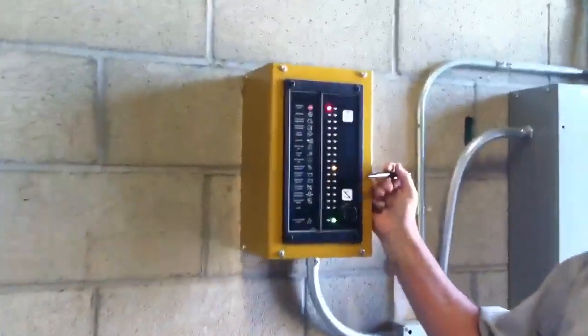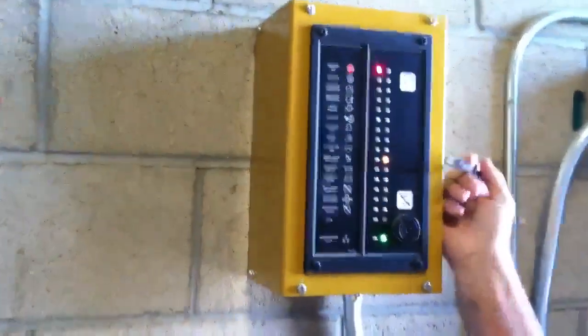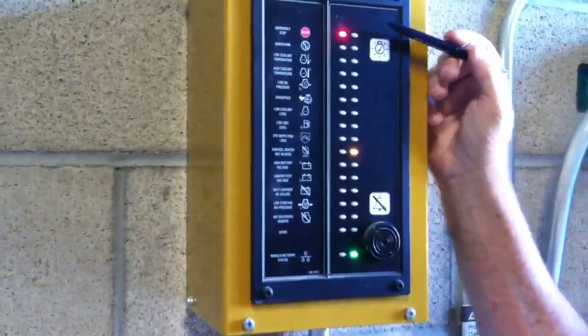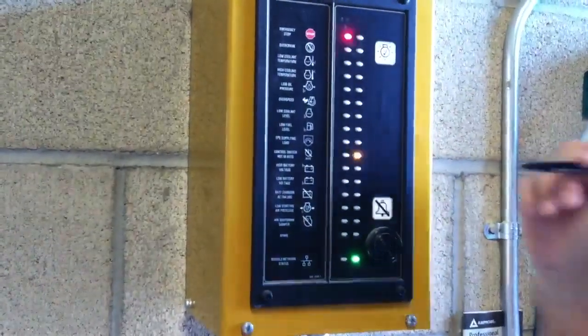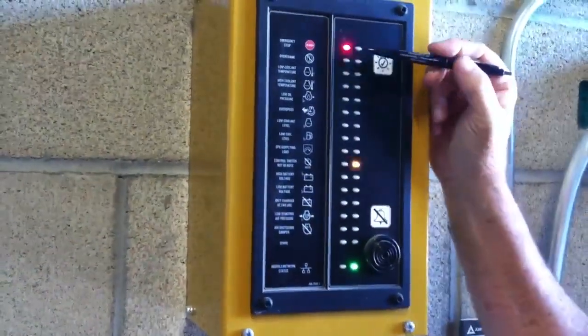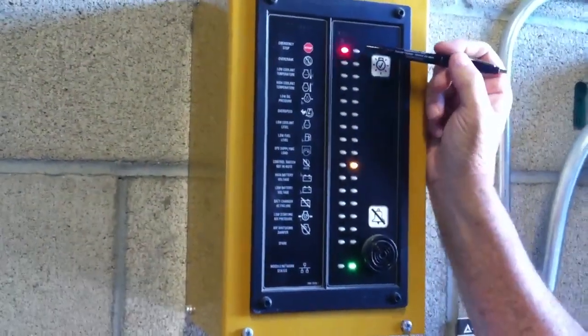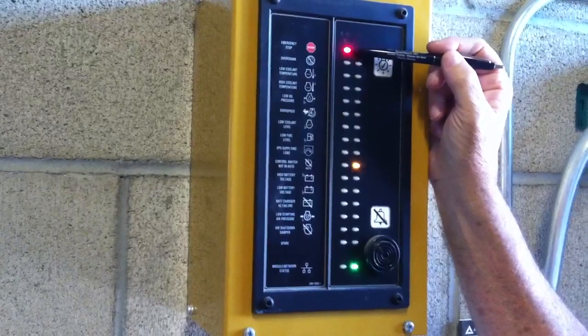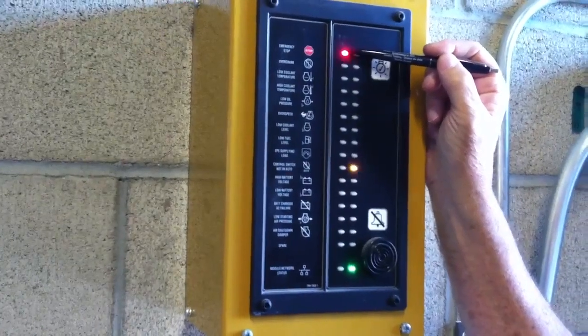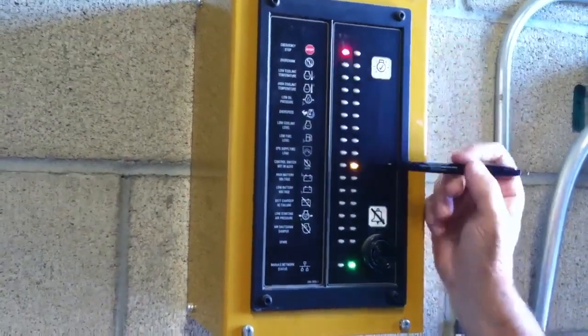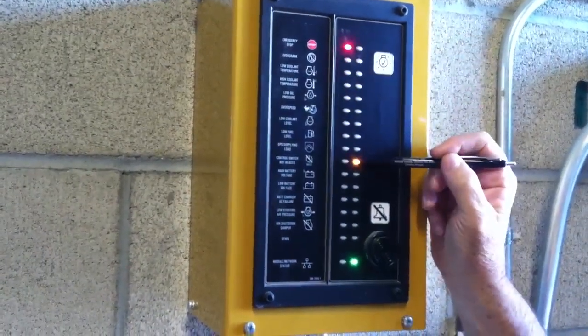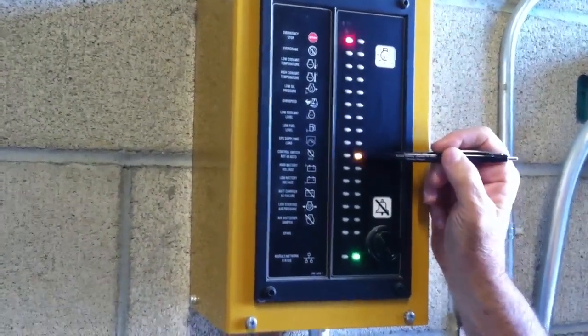This is our remote annunciator panel that's in the electrical room we noted when we were talking outside. And basically you note that we have an emergency stop that's active on here right now and a control switch not in auto.